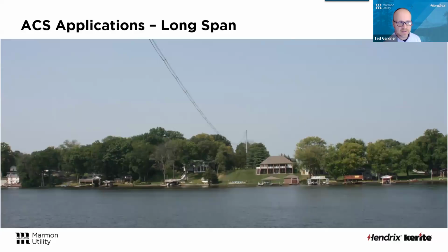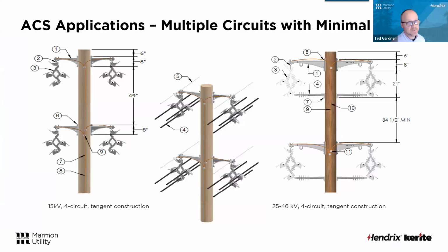The longest one we've done, we've got a 1,600-foot span over a lake in northwest Indiana. And this was, believe it or not, the cost of this project was about 25% of the subsea cable that they were originally looking at. Now those are pretty heavy duty poles. You can tell there's quite a bit of sag there, but it was about $250,000 compared to the original estimates, which were closer to $1 million to run the cable underneath the water. So it worked out really, really well. And that's been in service, I think, for going on 20 years now. It's been up there for a while.